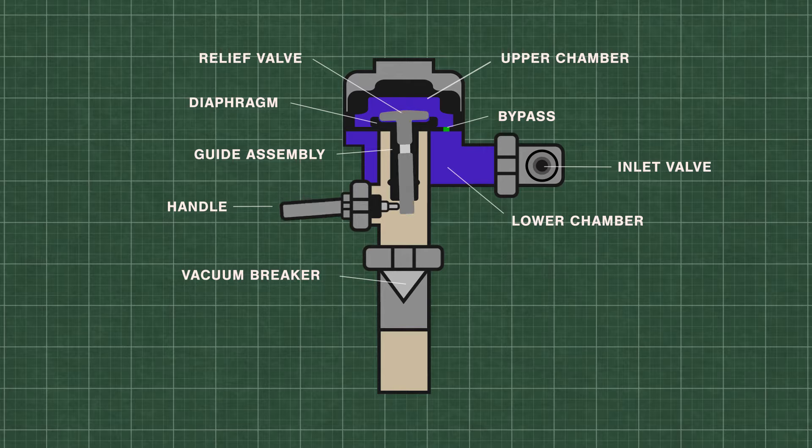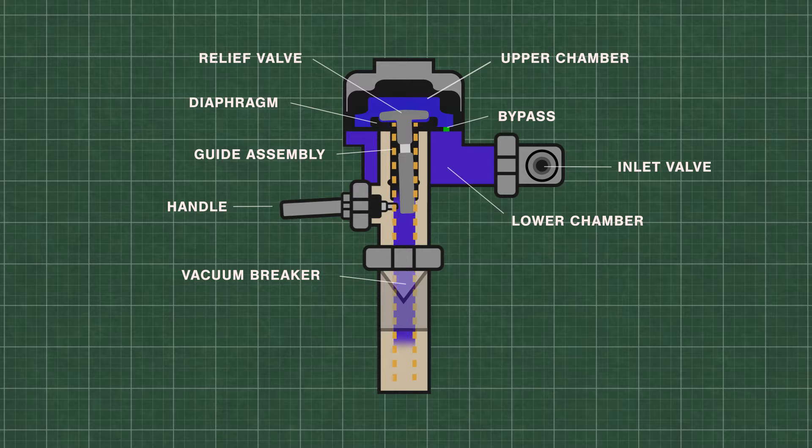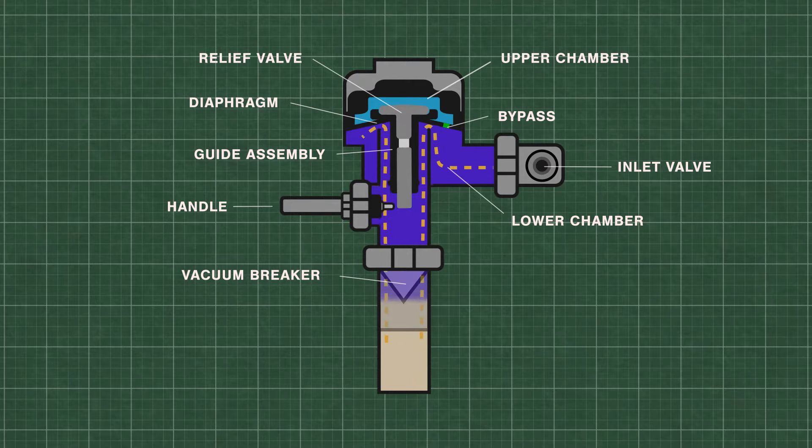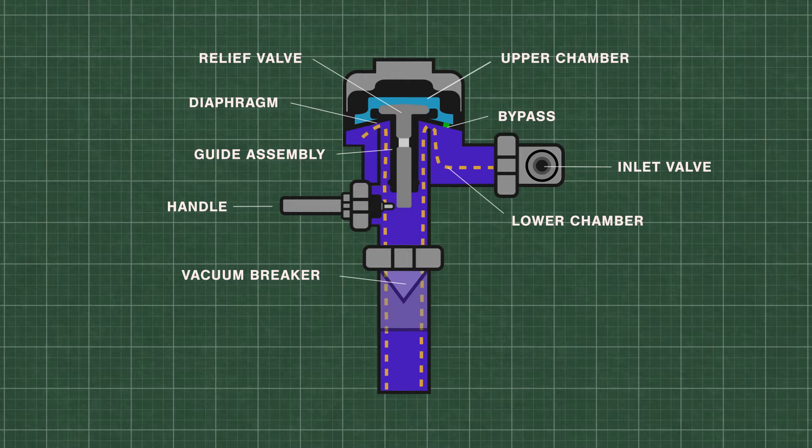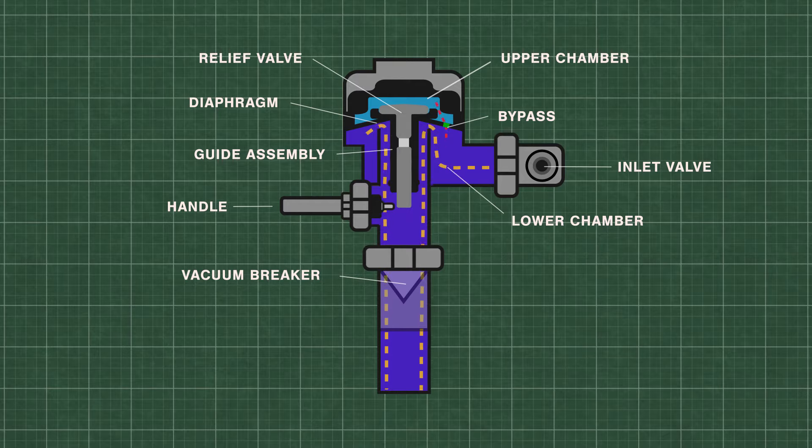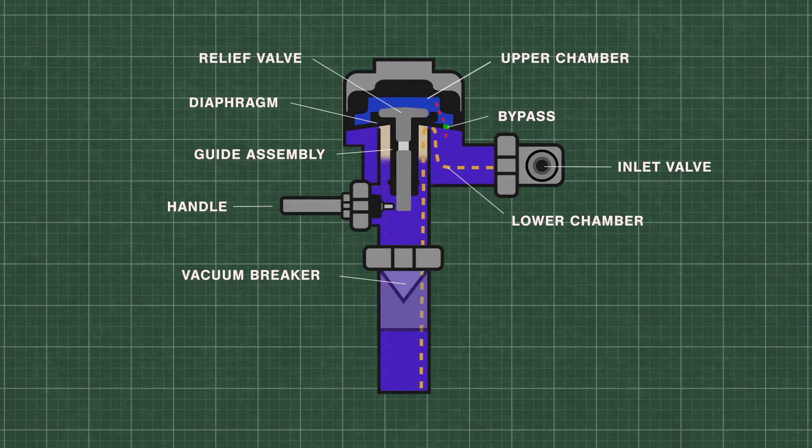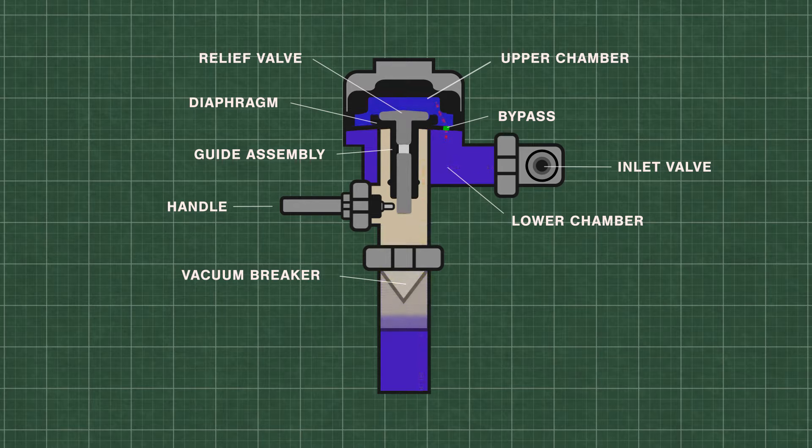When the handle is pressed, the relief valve opens and releases water from the upper chamber, which decreases the pressure. High pressure water from the inlet now lifts the diaphragm up and travels down the flush pipe. During the flush, some of the water is forced back into the upper chamber through a small bypass hole in the diaphragm. The flush continues until the pressure equalizes and pushes the diaphragm down onto the valve seat.